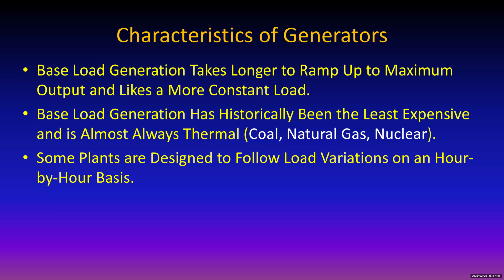You crank it up, and everybody knows that when you've got a gasoline generator rated at, say, 5,000 watts, that generator is perfectly happy to light up a 100-watt light bulb, because as long as it's cranking out 120 volts, 60 hertz, it's perfectly happy to run at 120 volts and 60 hertz and not deliver any current whatsoever. The only penalty you pay is it burns the gas and you pay for it. So the rotating generators that are fossil fuel are most efficient at somewhere around 80% of their peak load. And of course, when you come closer to peak load, they burn more fuel, because obviously the energy out has to be less than the energy in. There's something about the second law of thermodynamics that requires that.